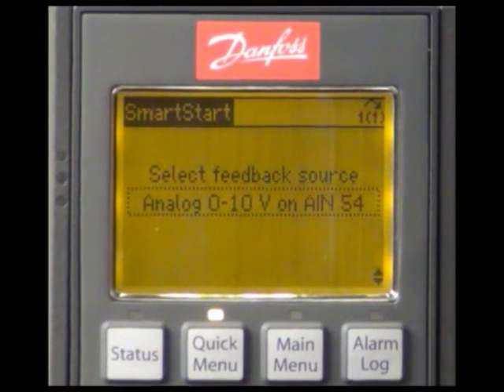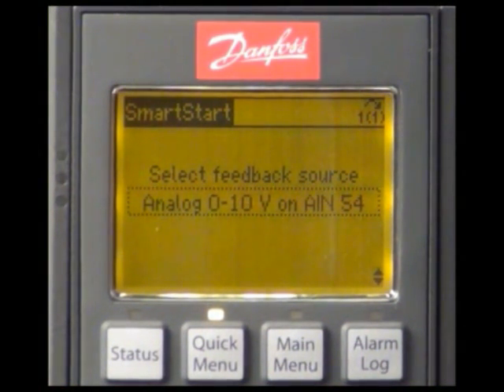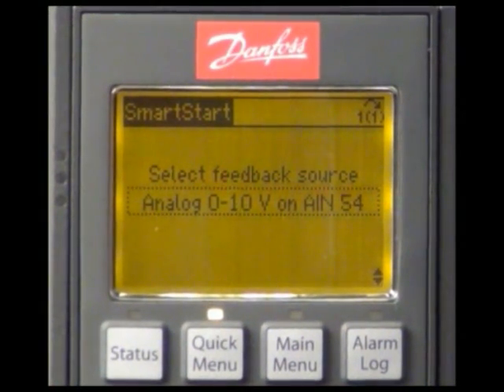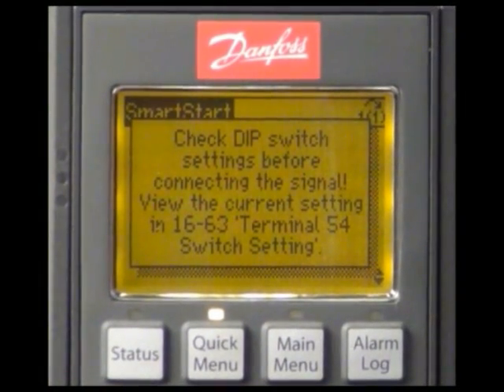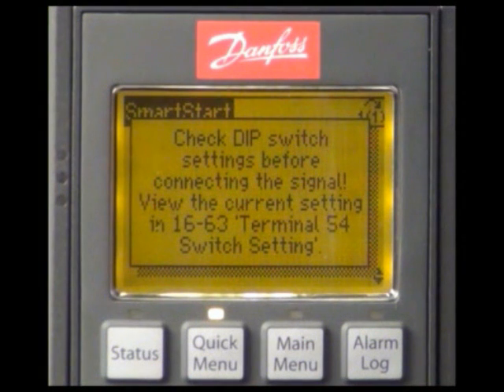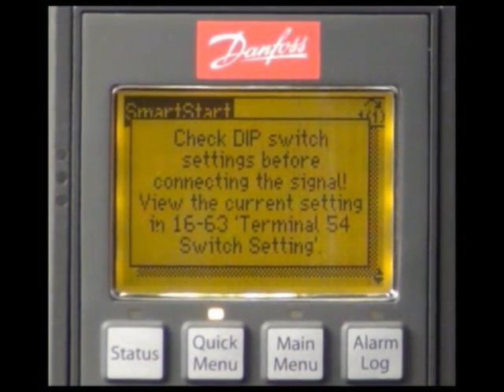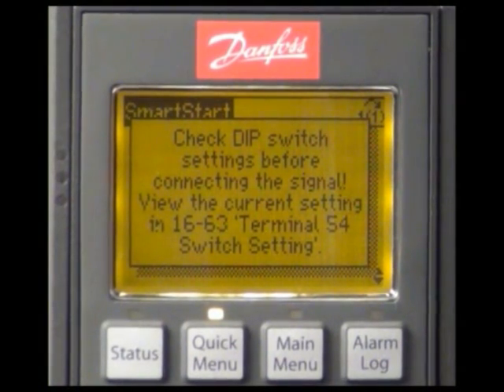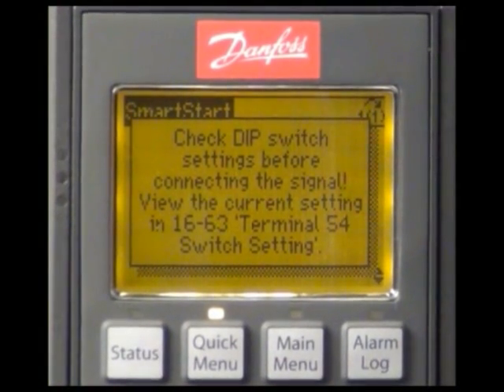For the feedback of the master drive, which is running in closed loop, we select the analog input 54. This screen asks us to check the dip switch of the drive which allows us to switch between voltage input and current input of the analog input for the feedback.